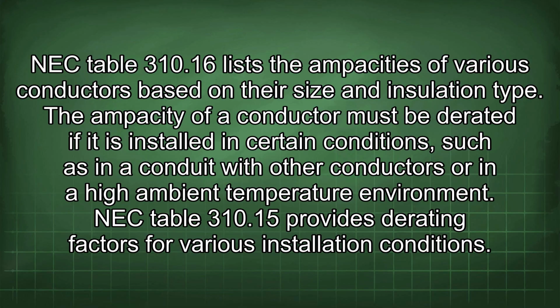The ampacity of a conductor must be derated if it is installed in certain conditions, such as in a conduit with other conductors or in a high ambient temperature environment. NEC Table 310.15 provides derating factors for various installation conditions.